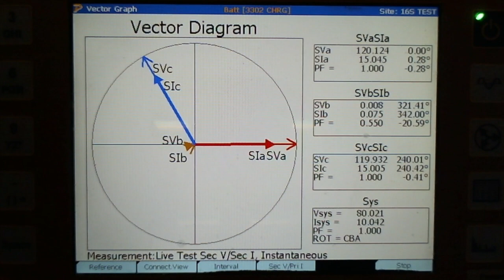So what do you guys want to do? We have no B phase voltage and no B phase current. So I'm going to check my transformers again on this one as well. What could happen on the transformer side? You could have a blown fuse on the transformer, just like I was saying on the other one. In the other simulation, if we still had the voltage, more than likely you've got something going on in your meter, right? Yeah, that's right. So this one is simulating an issue on the transformer side itself coming into the meter. It's not a meter problem. The meter socket is okay. This is something going on outside of the meter. So what we did was we measured voltage, we checked our current, and we verified it with our Powermaster.